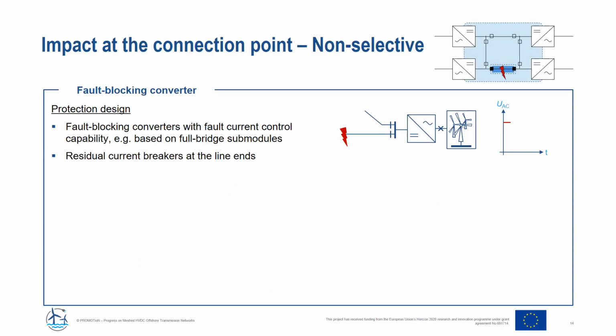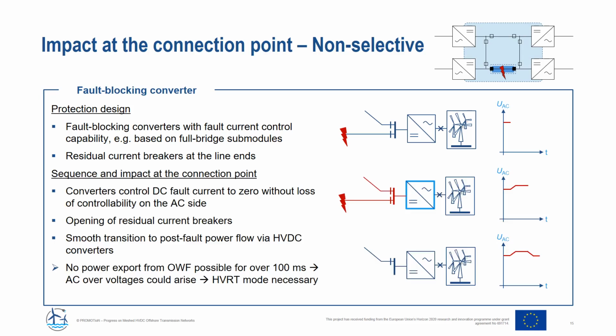Coming to the non-selective implementations of fault clearing strategies, the first strategy proposed here is based on fault blocking converters with fault current control capabilities, for example based on full bridge submodules. And this enables us to reduce the capabilities of the circuit breakers at the line end so that, for example, residual current breakers can be used here. So in case of a fault, the converters control the DC fault current to 0 without loss of controllability on the AC side. When the current through the breakers on the faulted line is small enough, the residual current breakers can open, and afterwards a smooth transition to post-fault power flow via the HVDC converters can be achieved by first ramping up the voltage and then the power.